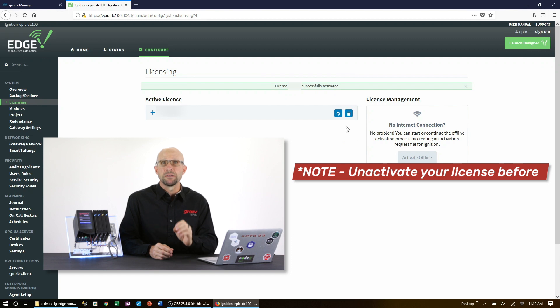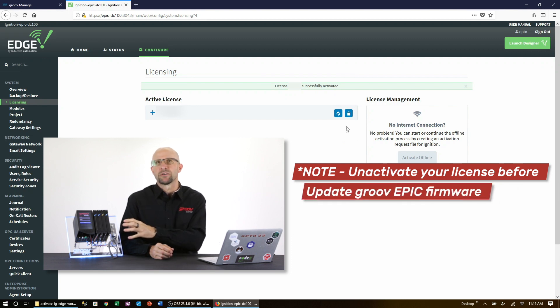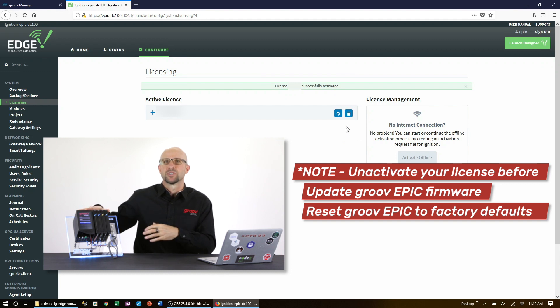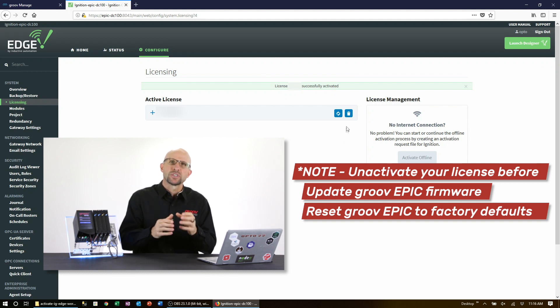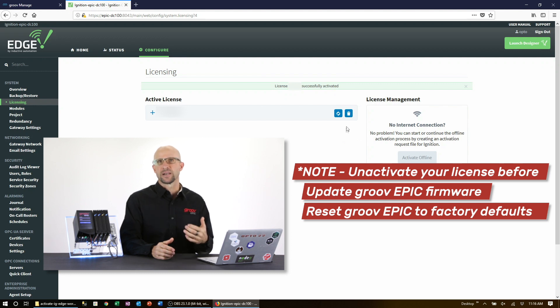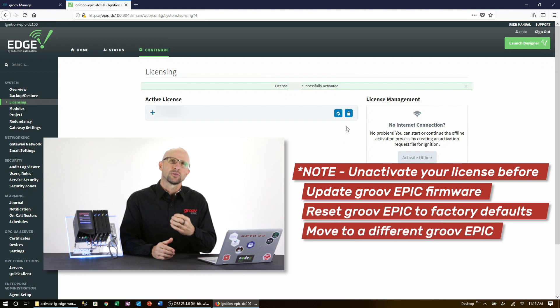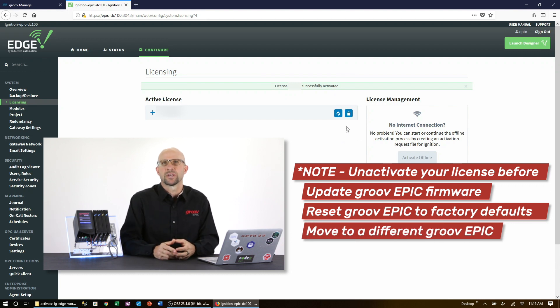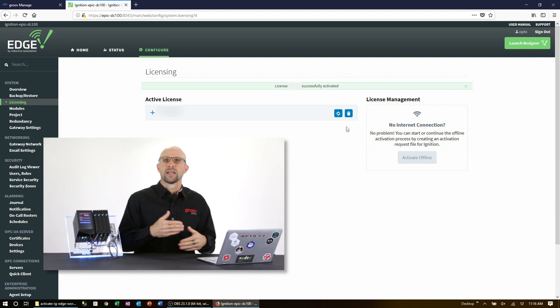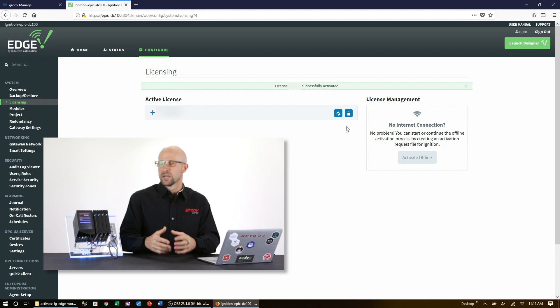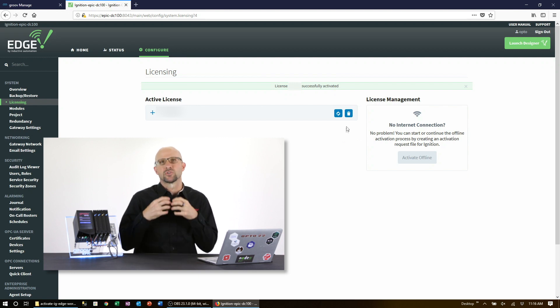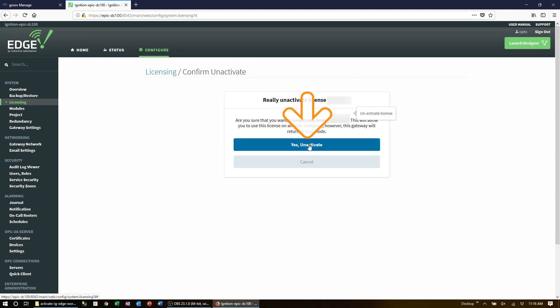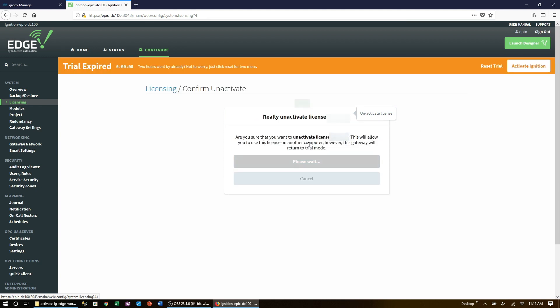Now it's really important to note that before you update your GroovEpic firmware or if you need to reset your epic back to factory defaults, you should first unactivate your license so that you can reactivate it after the update or the reset. You should also unactivate your license first if you intend on moving it to another GroovEpic. By unactivating and then reactivating, you avoid having to contact inductive to have the license reinstated. To unactivate, simply click on the trash can icon here and then click yes to unactivate.